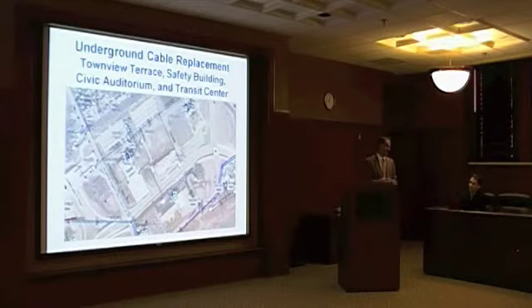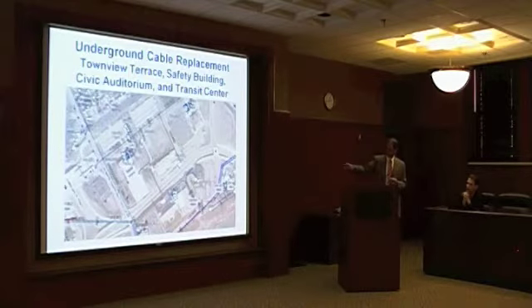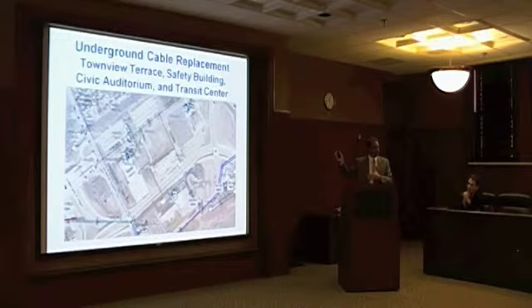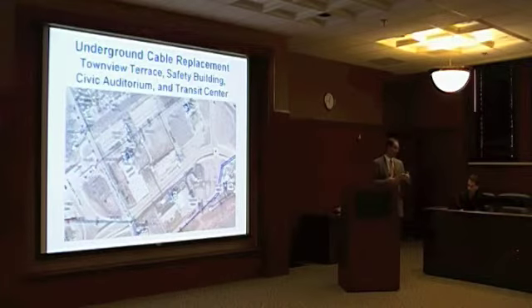Back this spring, we had a series of breaker operations in the substation that serves this area. Once we patrolled the area, we discovered the problem was within some of our underground cable. Because that's underground, it can take a long time to find the problem. We were able to isolate this section from our overhead customers and get their power restored fairly quickly, but these other customers were out for many hours while we investigated and made system changes. After those changes, we went about two months before another cable failure, which isn't uncommon on the underground system due to fault currents damaging the cable.